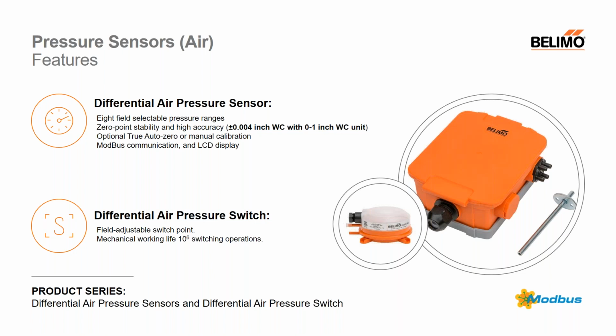Basically, as a filter ages, it gets clogged with more and more dirt, debris, and sediment. As a filter gets dirtier, of course, air is built up on one side of the filter, which innately increases pressure on the same side of that filter. As pressure increases on only one side of the filter, the differential pressure value across the filter will also increase.